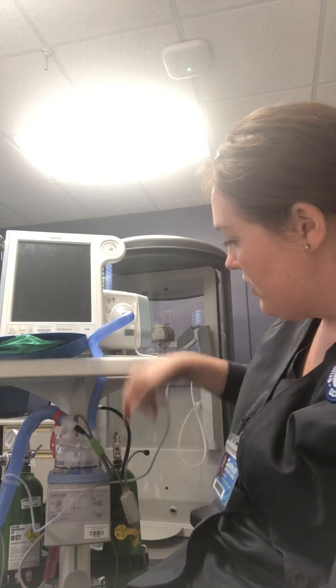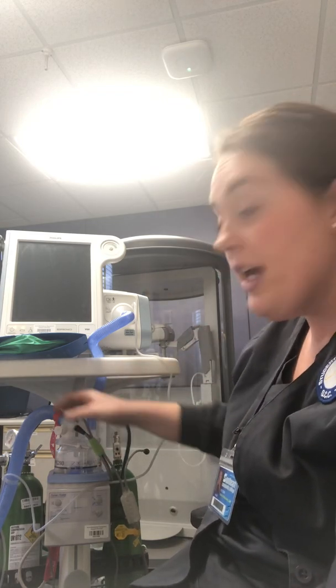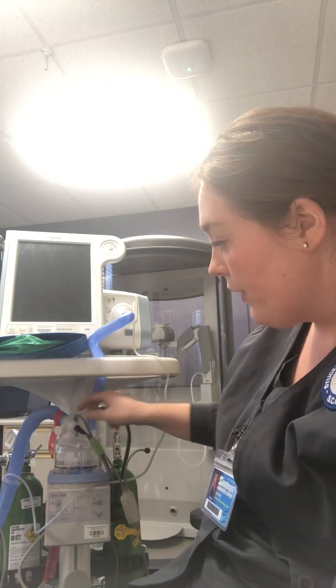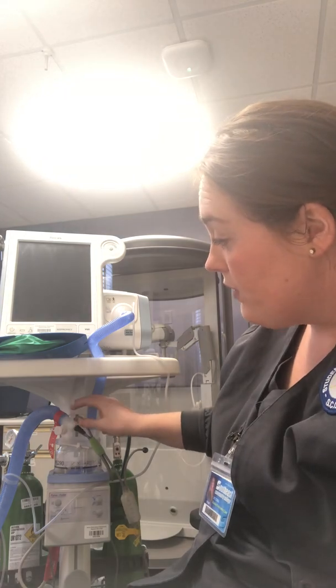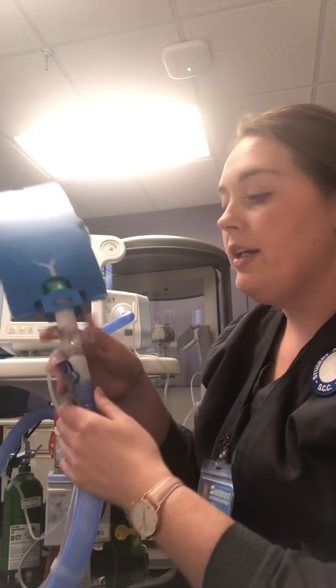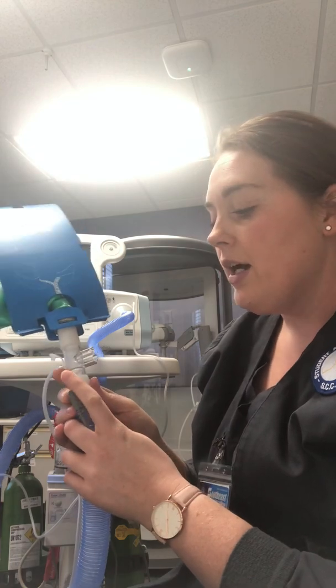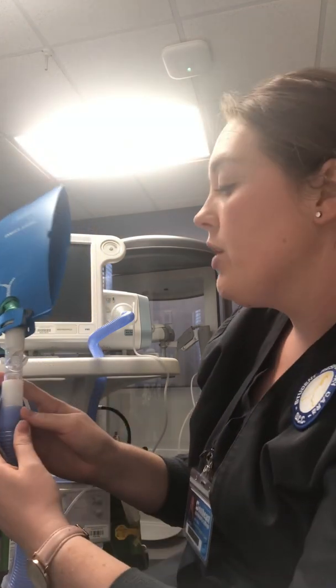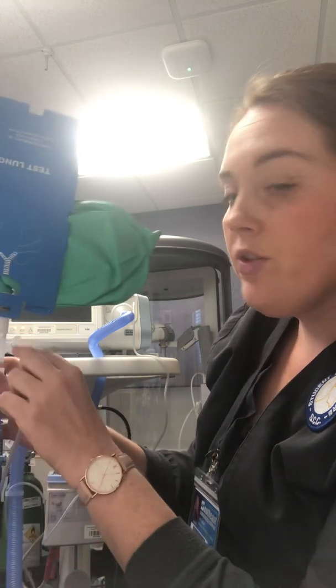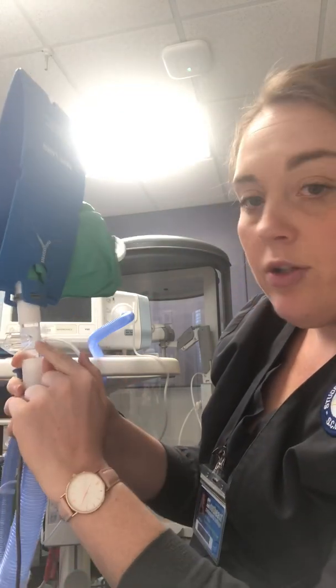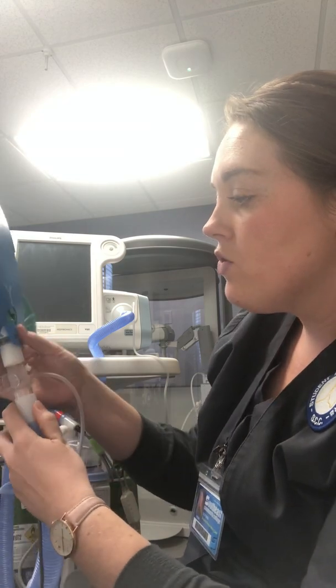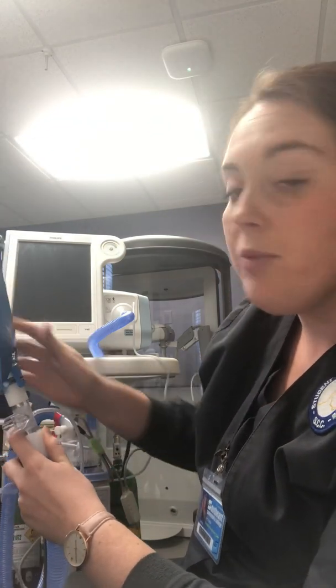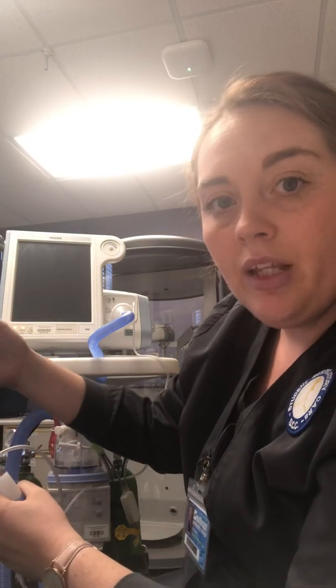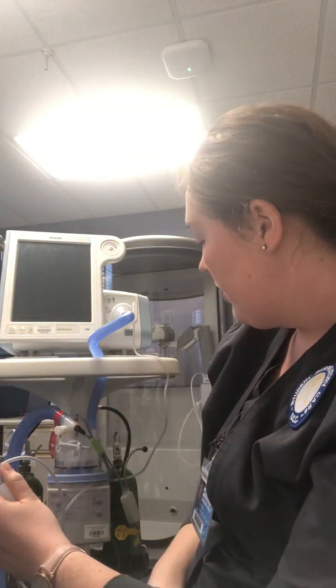You can notice that this is coming from the machine into the water. This side is the side that's going into the patient's circuit. So there is a temperature probe here on the top of the chamber, as well as a temperature probe here near the patient's interface to keep track of that temperature. You can also see that here's the pressure going to the patient, and we do have an exhalation valve. So this is normally where you would have your patient's mask, but I am going to have my test lung here instead. So we've kind of gone over all of these things you see on the outside.